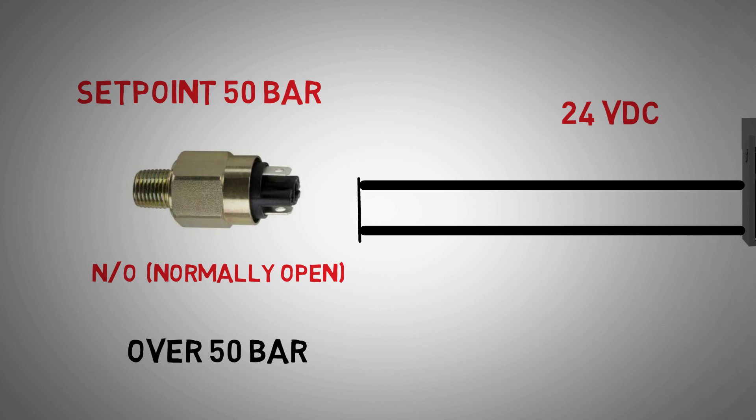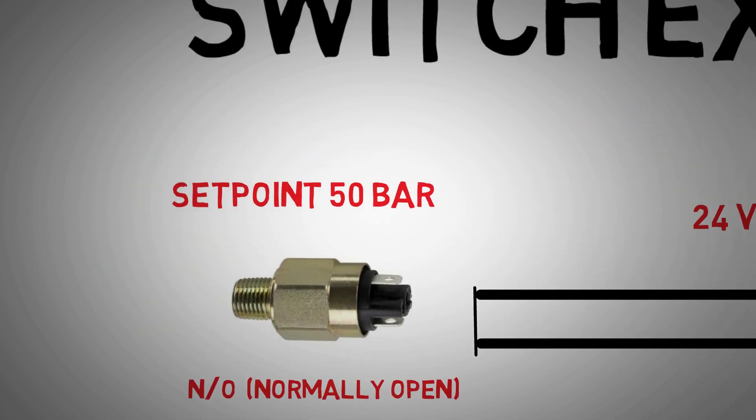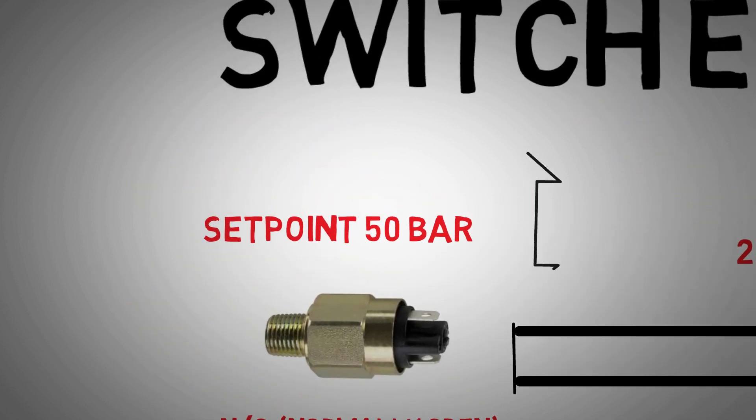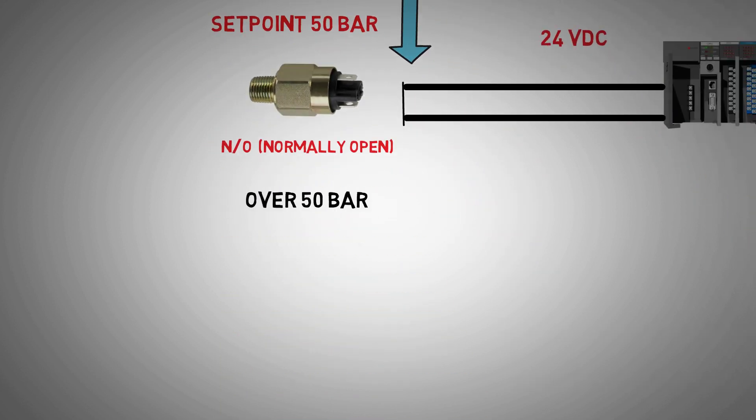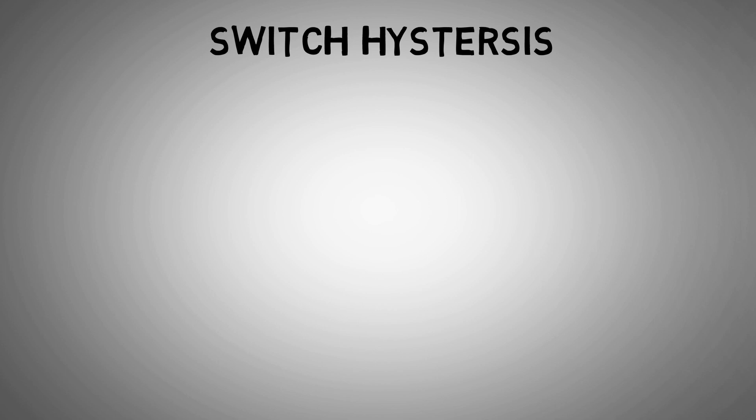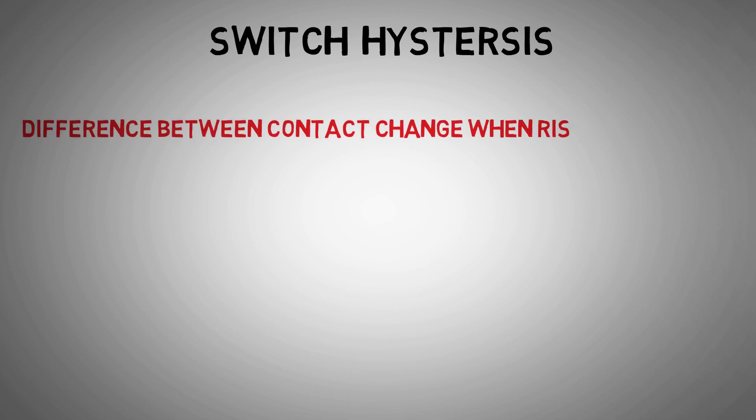When talking about the set point of a switch, it's important to know if this is set up to respond to a rising or falling process condition. Mechanical switches, such as in a pressure switch, will not open and close exactly at the same pressure set point. There will be a slight difference in pressure required to activate the switch than what is required to deactivate the switch.